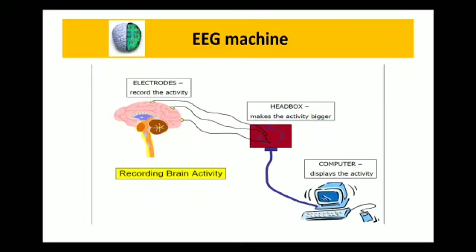Then we have electrodes. We have disposable electrodes, reusable electrodes, needle electrodes. Disposable electrodes have a central snap that is made up of silver chloride. Reusable ones are smaller. They can be placed closer to the skin, and initially they are costly, but in the long run, if you compare the cost, they are more budget friendly than the disposable ones.